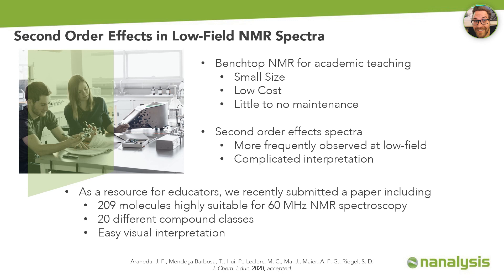It should be noted that low-field instruments by nature are more prone to produce NMR spectra with second-order effects. In contrast to first-order spectra, those with second-order effects cannot easily be interpreted by eye and some information is not extractable. While there are plenty of compounds that do not show second-order effects at low field — just like the spectra discussed in this presentation — there are others that do. This can be concerning for educators who do not want to add this extra layer of complexity. To help address this concern, we recently submitted a paper presenting a list of more than 200 molecules from 20 compound classes whose NMR spectra can be visually interpreted using 60 MHz instruments.